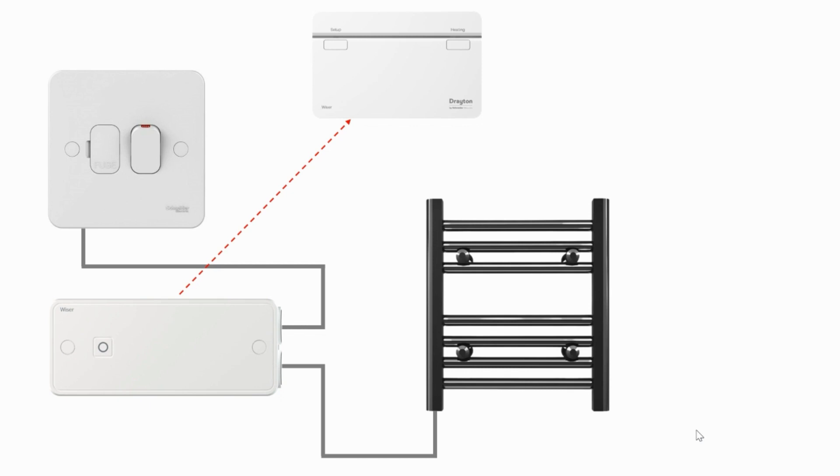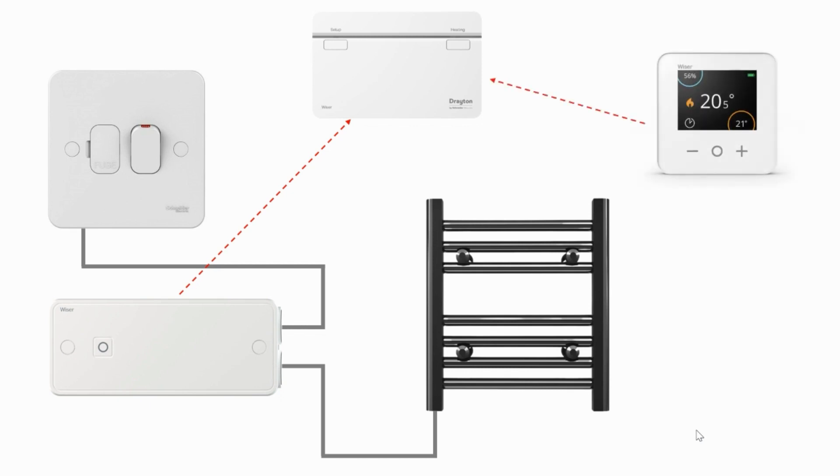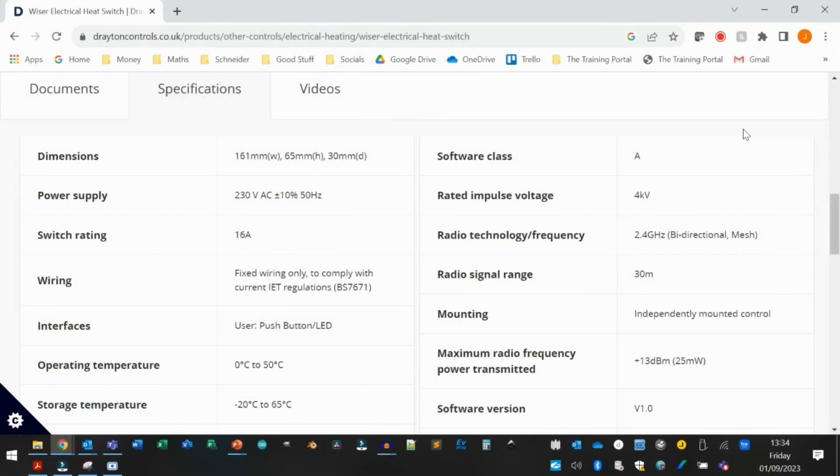It's important to remember that these are not standalone controls. There does need to be a Wiser Hub R fitted as part of the system. The maximum permitted load per Wiser electrical heat switch is 16 amps resistive. These are not suitable for use with inductive loads.